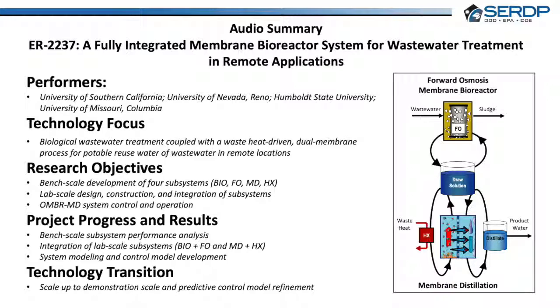During long-term OMBR operation, carbon and nitrogen removal was achieved in a single reactor by alternating between aerobic and anoxic bioreactor conditions. Results from long-term testing using a high-strength wastewater showed 98.4% removal of chemical oxygen demand and 90.2% removal of ammonia as nitrogen. Physical design aspects and process controls for system integration, as well as procedures for wastewater treatment with the single-stage OMBR system, were established.